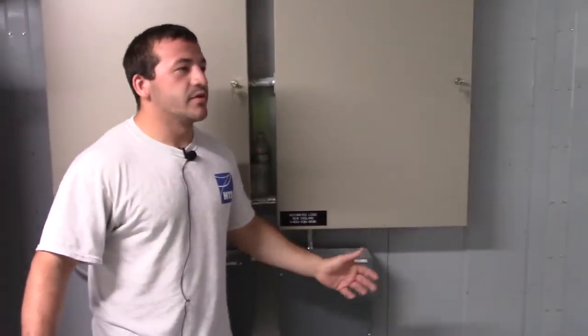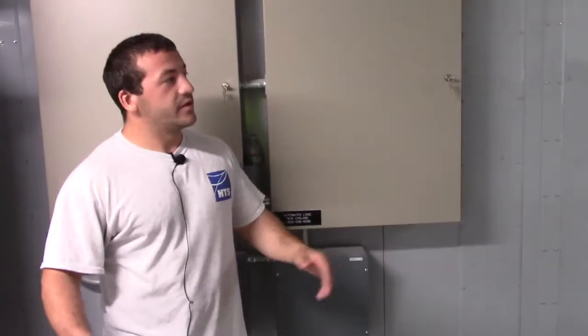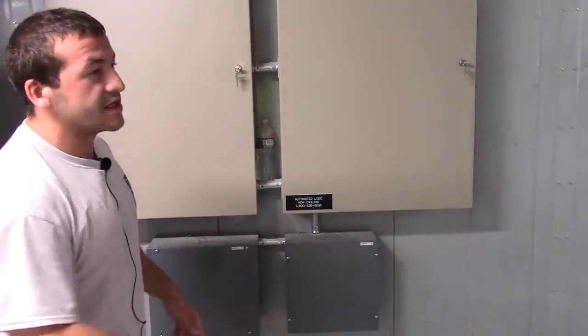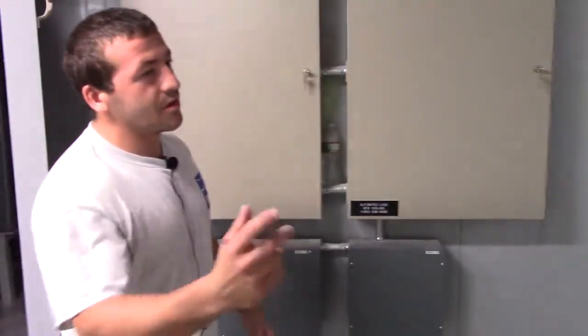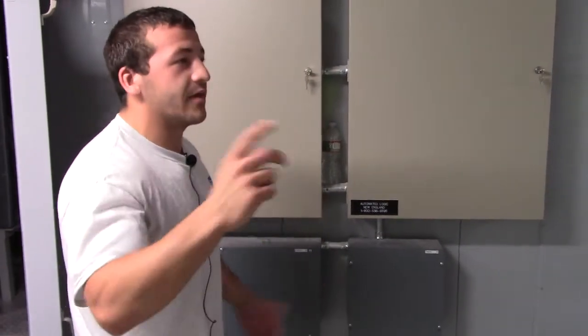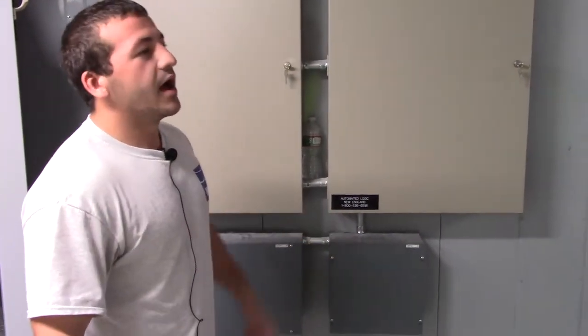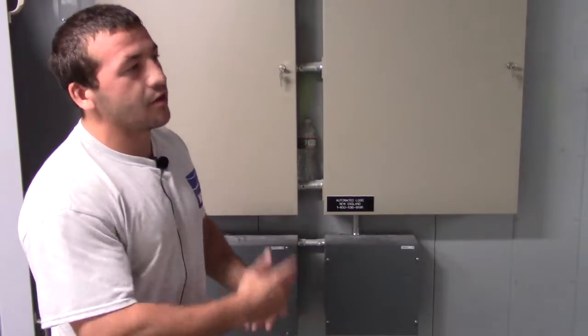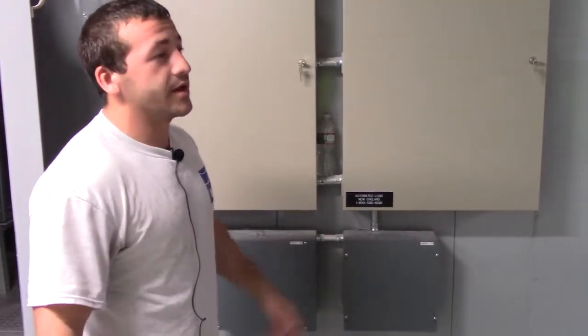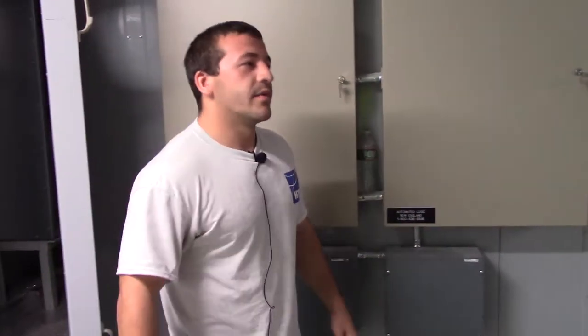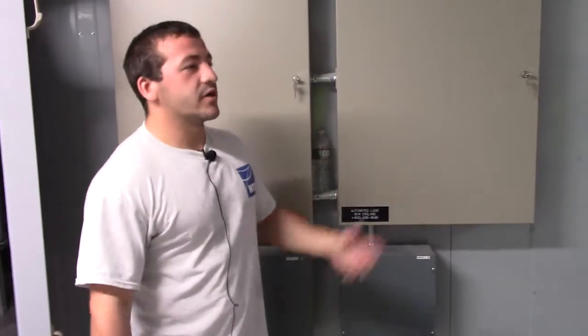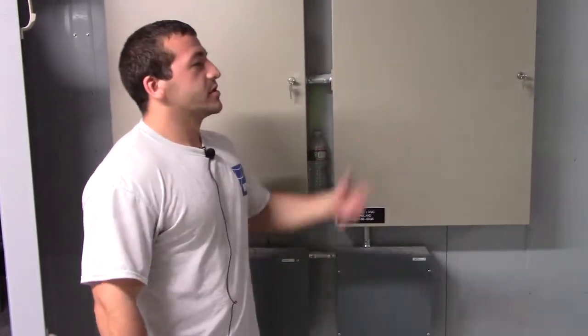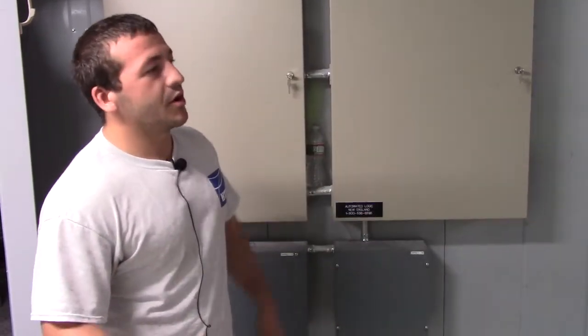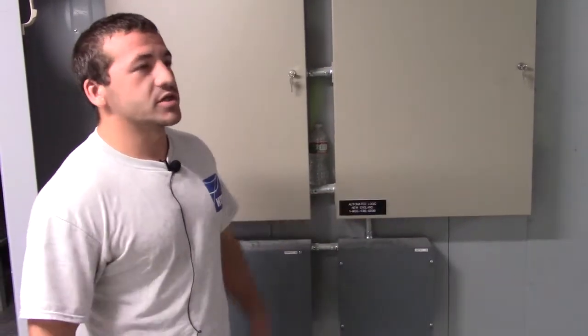So when you come up to the unit, if you're going to shut it down, you can either shut it down by shutting down all the VFDs, each one separately, or you can go to the BMS system and just shut them down that way, whatever's easier for you. Obviously, if you shut them down this way, you might get an alarm back to the BMS that might have to be cleared in order to restart it. And then same thing, reverse order to restart the unit.